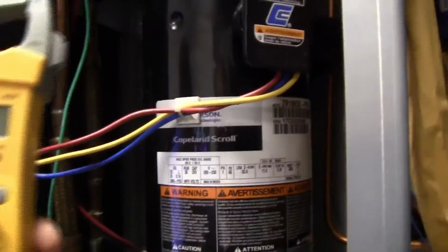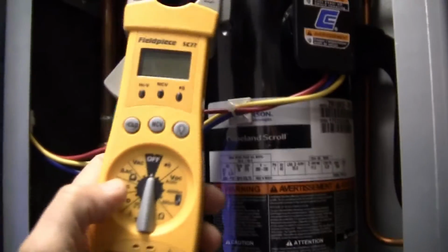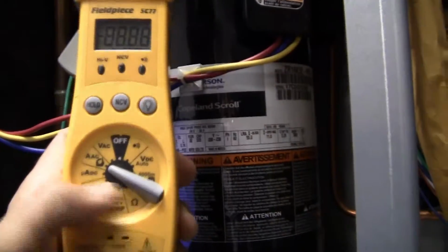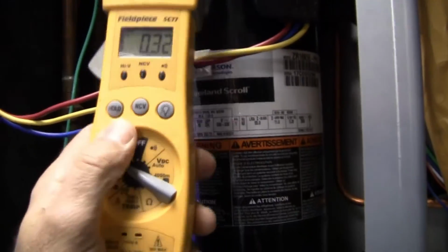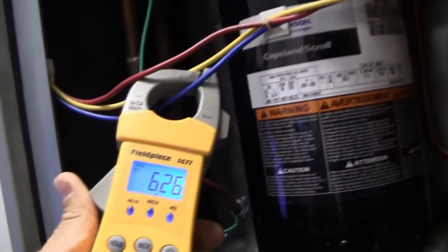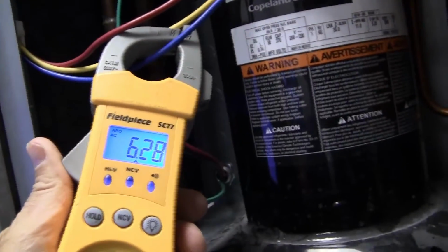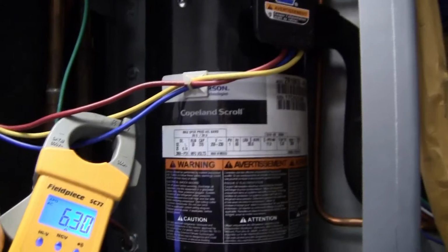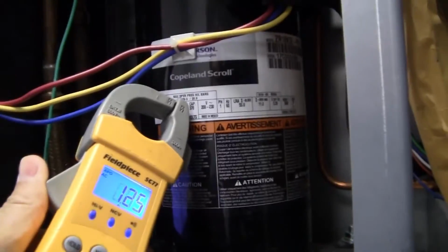Now, when you come over to the compressor, I'm going to take my Fieldpiece and put it on amperage AC. That's that one right there. I've got the backlight on, and I'll throw it on a lead here. You can see we're pulling about 6.2 amps on this Copeland scroll compressor. So obviously that compressor is on, and the fan is on, I can see it turning right there. So the unit's operating.